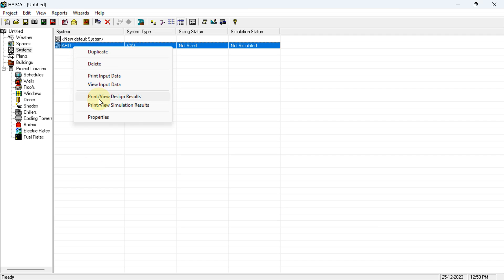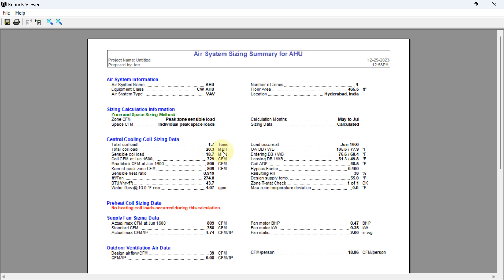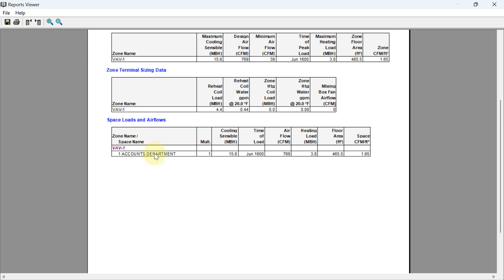To see the results, right-click, select Print View, then Design Result, and hit preview. Go to the next page to find account department. Under Space Load and Airflow for the VAV system, cooling sensible is showing 15.6 MBH. Dividing by 12 gives approximately 1.3 TR. So after adding the partition wall, the cooling load has increased to 1.3 TR and supply airflow is now 769 CFM.